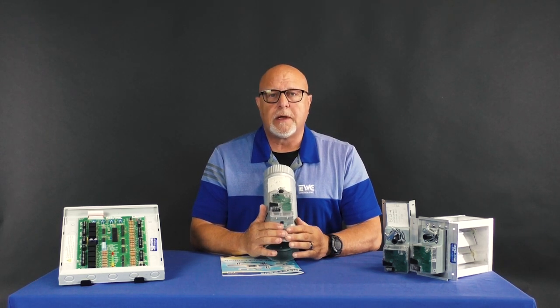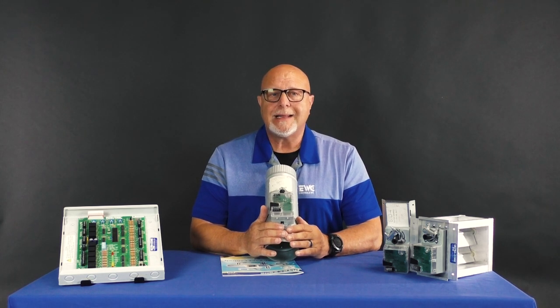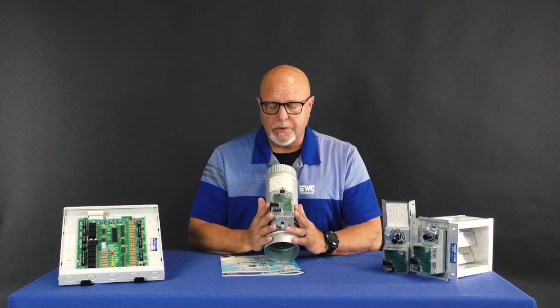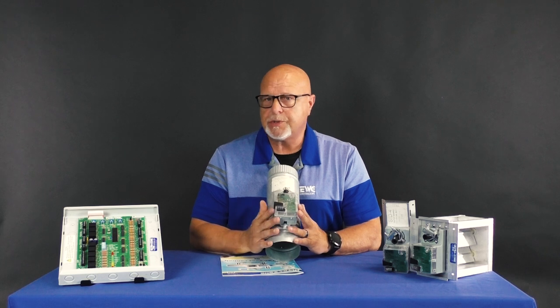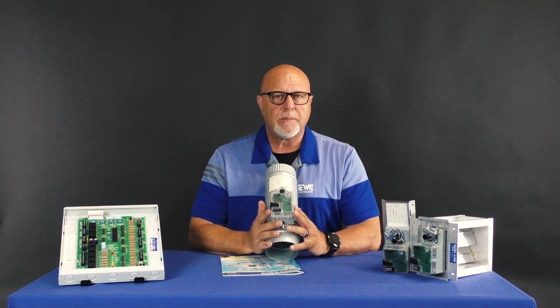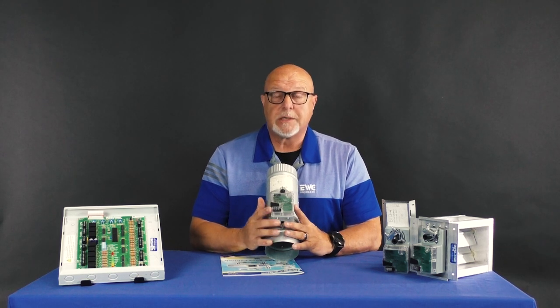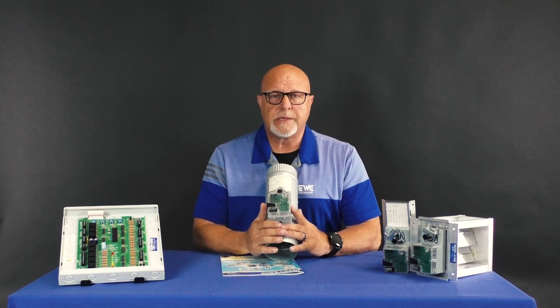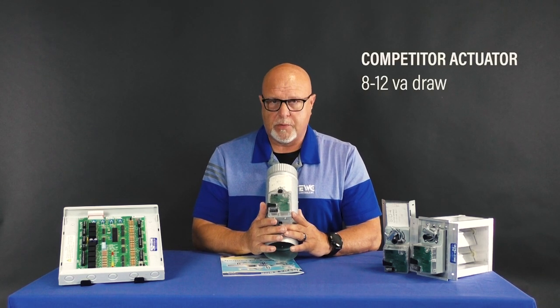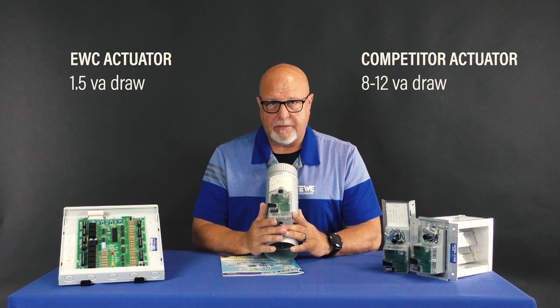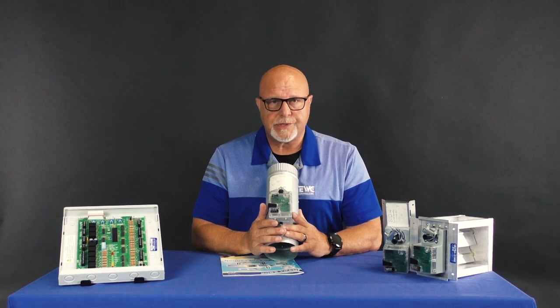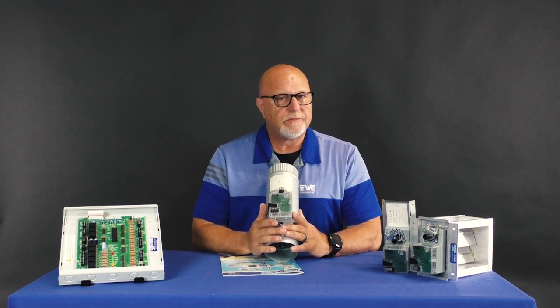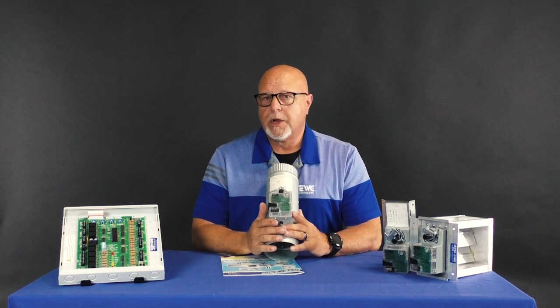Another nice feature that we have incorporated onto this damper is our very low amp draw. In a new construction situation where you only have 2 to 3 dampers, it really doesn't come into play very often. But when you get over 3 dampers, my 2-wire competitors out there, because they draw so much power, draw anywhere from 8 to 12 volt amperages. We only draw 1.5, allowing us to put many dampers on a 40 VA transformer without any additional relays, without any additional wiring. This is very crucial when you're in a retrofit situation or anytime you're over 2 dampers. With the spring return dampers, they have to add add-on transformers and relays, which is very commonly known as a wiring nightmare.